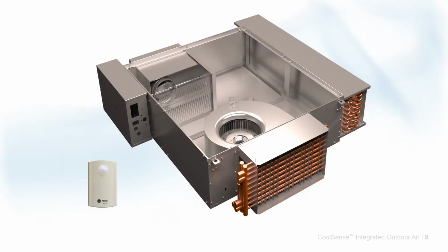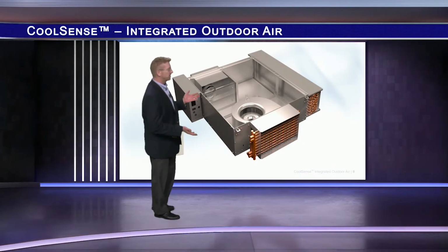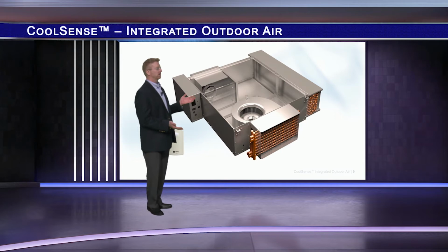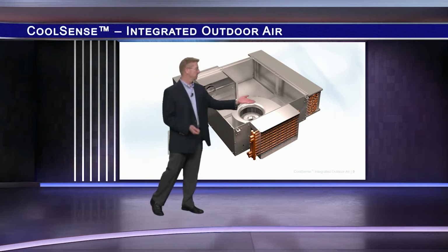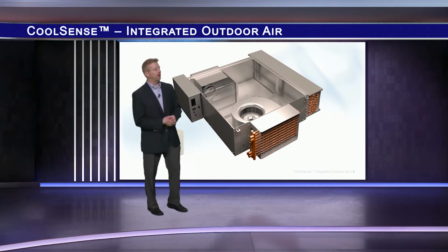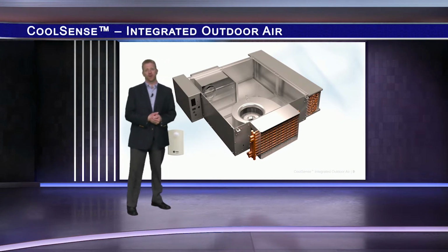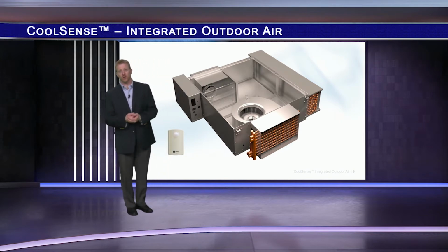Let's take a closer look at the sensible cooling terminal unit used in the CoolSense system. At first glance, this looks like a series fan-powered VAV box, but look here, a chilled water cooling coil mounted on the inlet from the ceiling plenum. So how does this work?